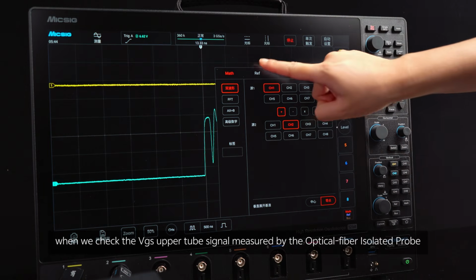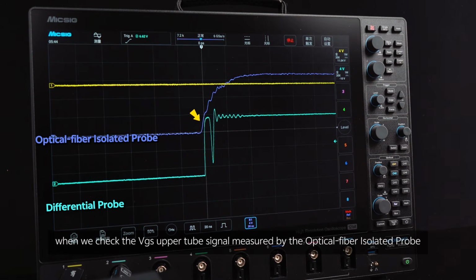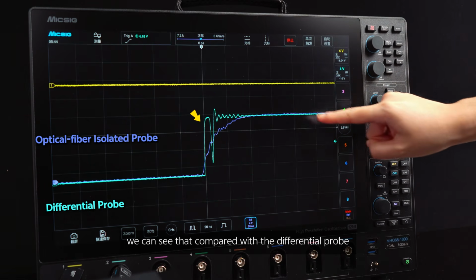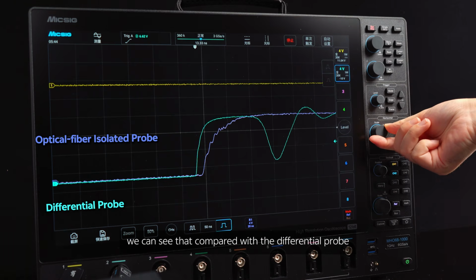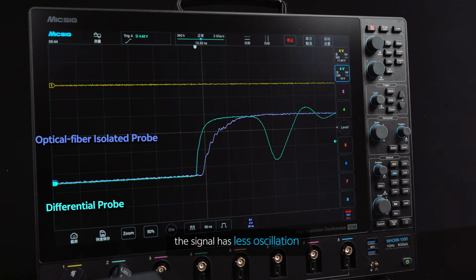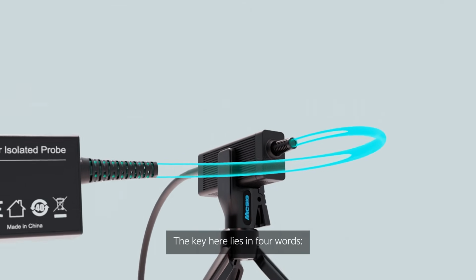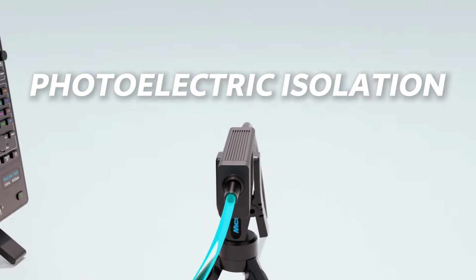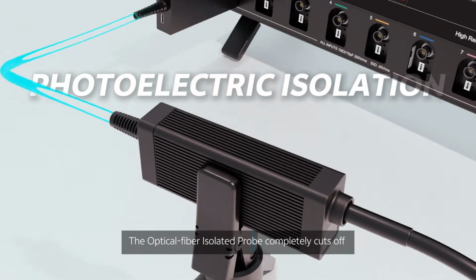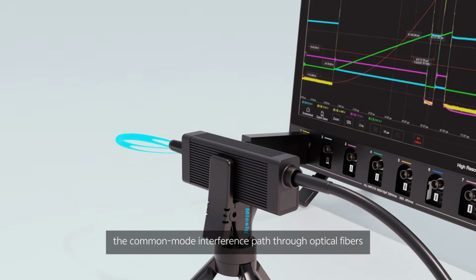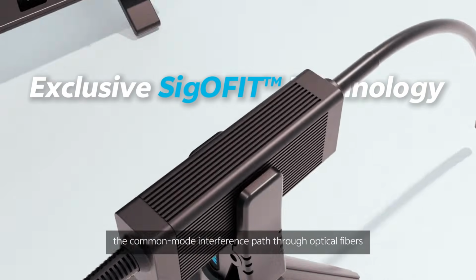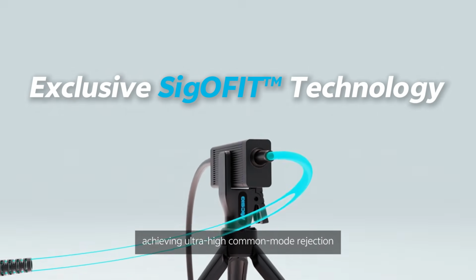Next, when we check the VGS upper tube signal measured by the optical fiber isolated probe, we can see that compared with the differential probe, the signal has less oscillation and displays a more authentic signal. The key here lies in two words: photoelectric isolation. The optical fiber isolated probe completely cuts off the common mode interference path through optical fibers, achieving ultra-high common mode rejection.